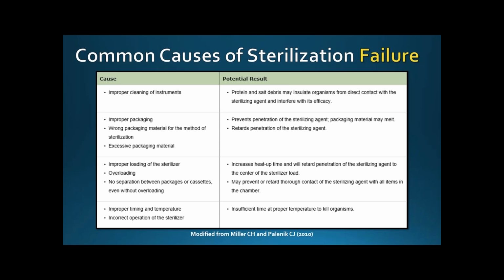If you have improper loading of your sterilizer, too many instruments in there, then you are not allowing the steam to fully penetrate everywhere. And again, if you don't put your chemical indicators in the right place, then it might give you false assurance that you had proper penetration of the steam.